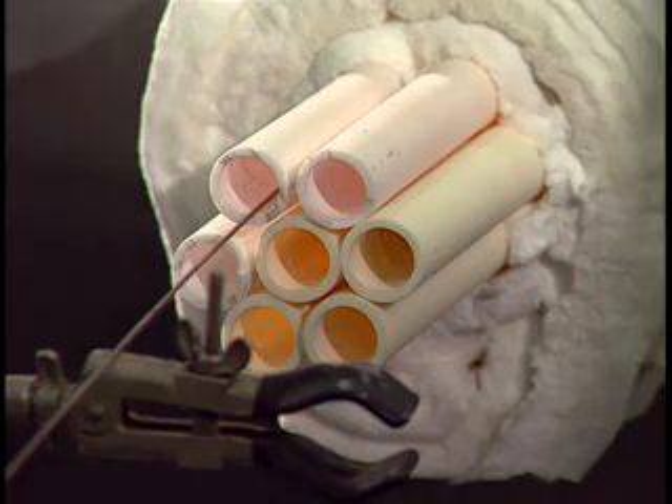We've tested Hydro-TCs in our two furnaces at 1200°C and at 1400°C for 4,000 hours. They drifted by less than 2% during the entire 4,000-hour test. Type N and Type K thermocouples tested at the 1200°C test drifted within 2% in the first 200 hours, and in the 4,000 hours they were tested, they drifted by over 100 degrees C. Clearly, Hydro-TCs are an improvement in high-temperature thermometry.